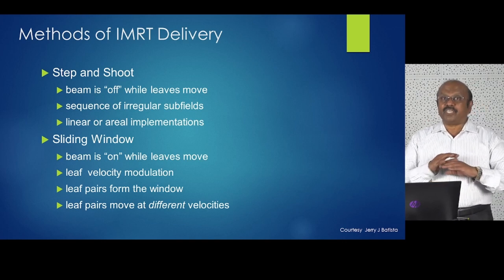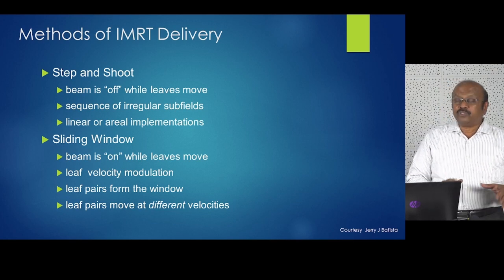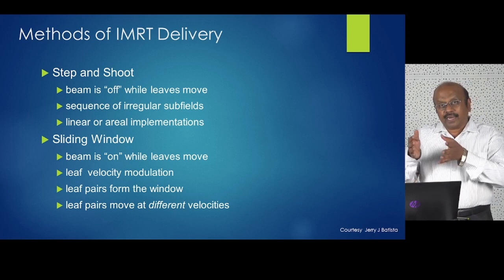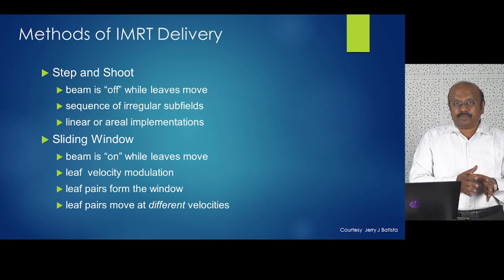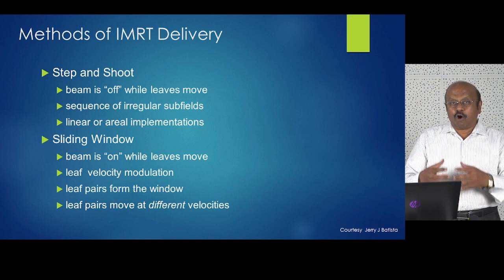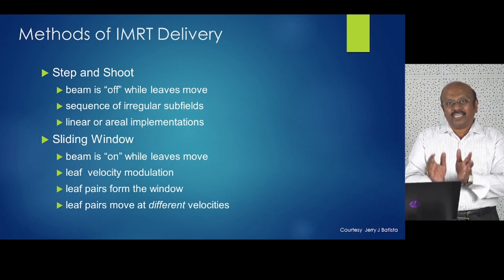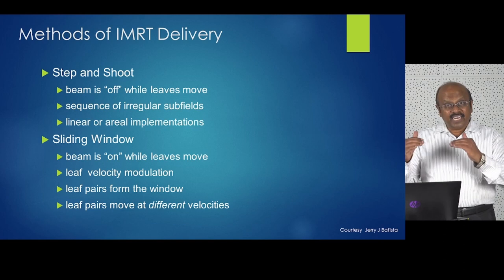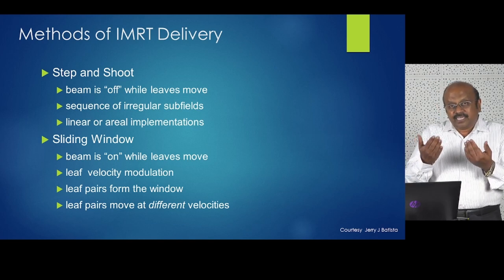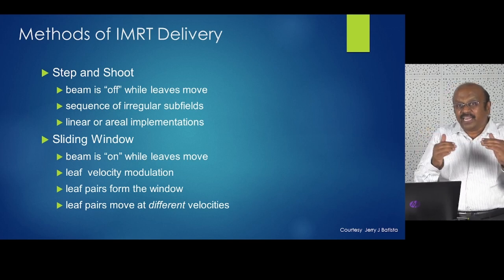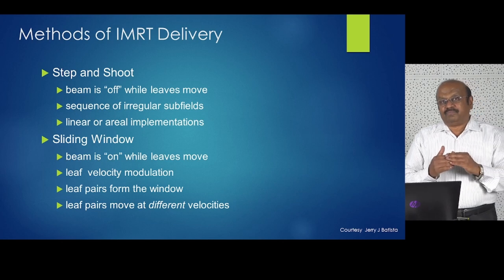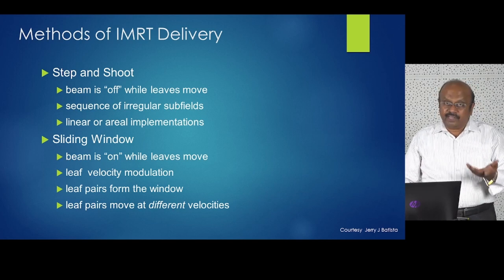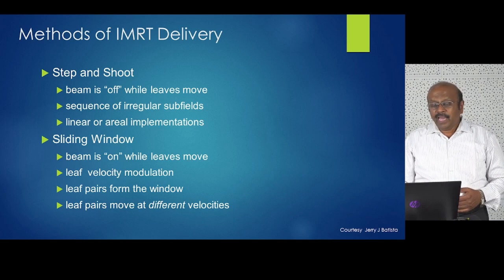In step-and-shoot, the beam is off when the leaves move. The leaves form a shape, the beam is on and irradiates, then the beam stops, leaves form another shape, and the beam is on again. The segments or shapes are formed while there is no beam; when completely formed, the radiation beam turns on. In sliding window, when the leaves move the radiation beam is on. The fluence map is obtained by varying the velocity and position of the leaves, including which leaf opens and closes.